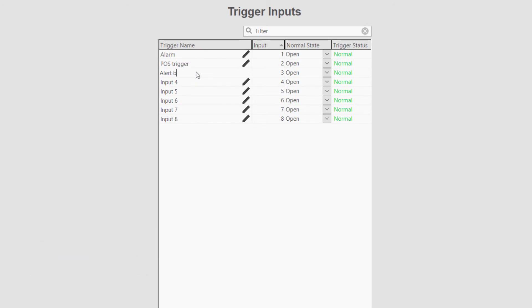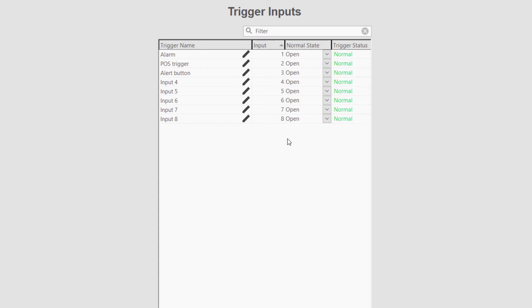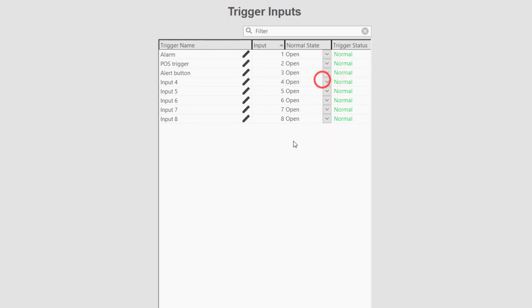The configuration of these inputs allows a user to select the normal state of the input, either open or closed. To detect an event that triggers when a nominal voltage is present on the inputs, set the normal state to open. This will tell the system that this particular input is in an alarm status when a voltage is detected. If a voltage is usually present and you wish to detect a break in that current, set the normal state to closed.